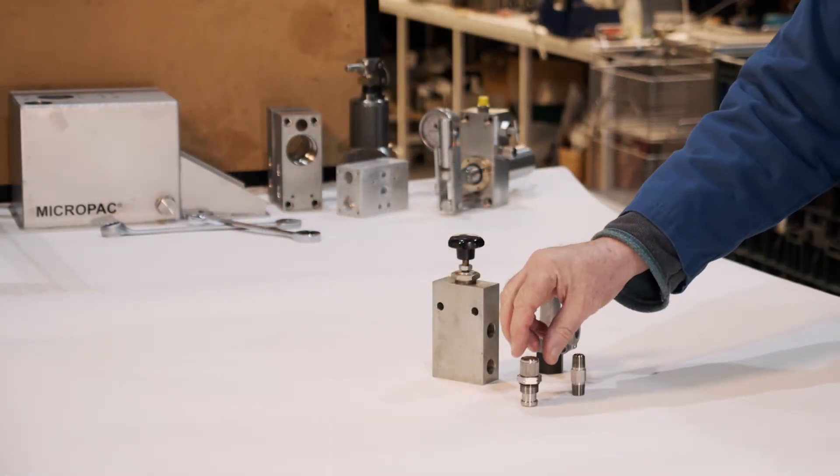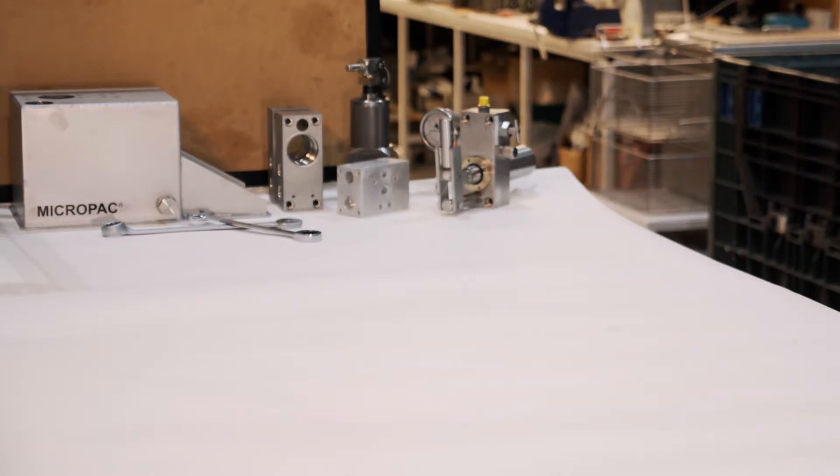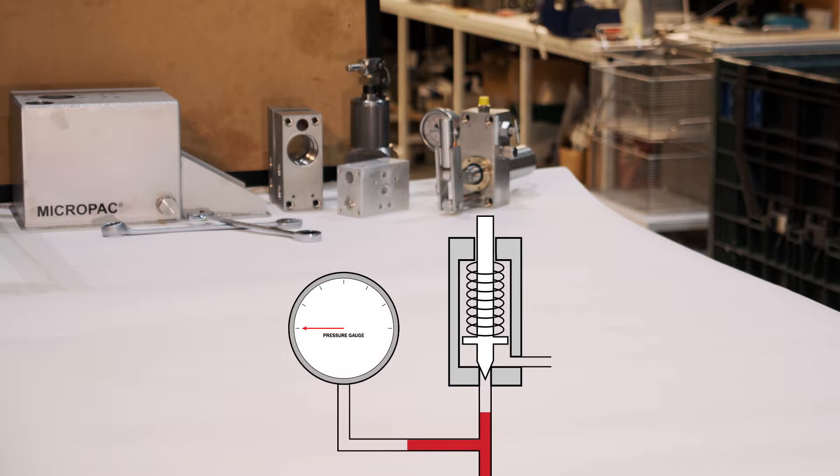I'm looking at this little cartridge relief valve that we fit into our MicroPAC pumps. Let's look at the basics of it. A plunger with a cone is pressed into an orifice using a spring. This seals and won't let flow past.